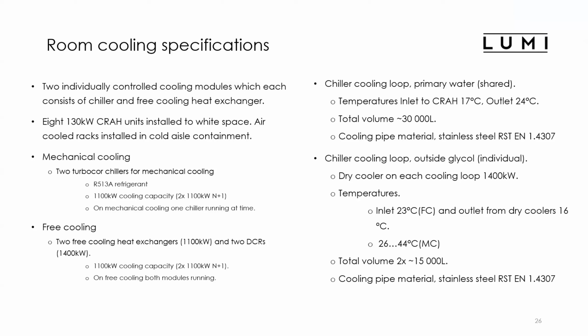Okay, so this room cooling, which we have for the air-cooled cabinets in the data center, we have 2 individually controlled modules, which consist of chiller and free cooling heat exchanger. We currently have 8 130 kilowatt CRAH units installed in the data center. Chillers are equipped with Turbocor compressor, which is advanced technology to deliver high efficiency and low sound levels in compact footprints. So these are quite good chiller devices. Those are using R513A refrigerant, and each one of these has 1.1 megawatt of cooling capacity.